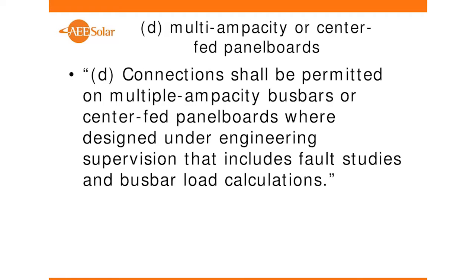And then the last item here is multi-ampacity bus bars, center-fed panels. So connections, the way the 2014 code is written is that connections to center-fed panels could be done under engineering supervision. So we have a bunch of jurisdictions in the state of California right now that if you get a letter from an engineer, they're okay with it.